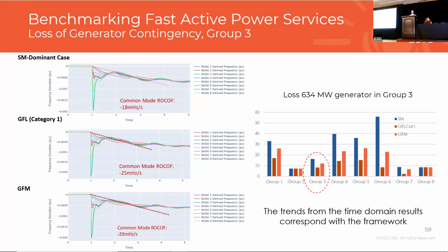Looking at a few metrics, a couple of things stand out. One is that even in the common mode response of the system, removing those fast services means the rate of change of frequency increases, changing essentially proportionally with the level of fast active power services, which are most relevant in this time frame. It's 18 millihertz per second in the synchronous machine dominant case, negative 25 millihertz per second in the grid-following case, with grid-forming falling in between.